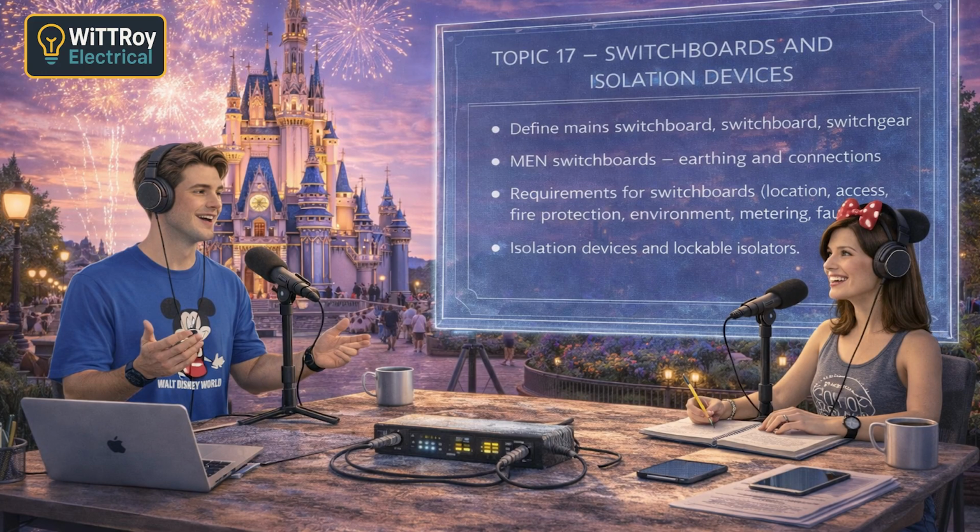Okay. Now let's talk about switchgear. I always mix this one up. That's very common. Switchgear refers to the devices that do the switching and protection. So, breakers, fuses, isolators? Exactly. Circuit breakers, fuses, isolators, load break switches, contactors, all of that is switchgear. So, the switchboard is the panel and switchgear is what's inside it. Perfect. That's exactly how to remember it.